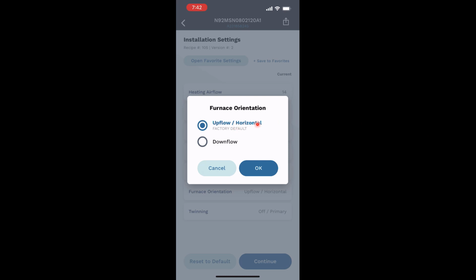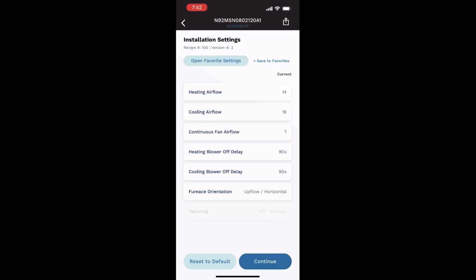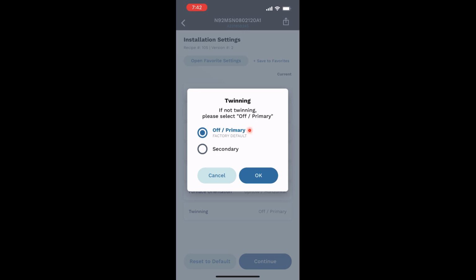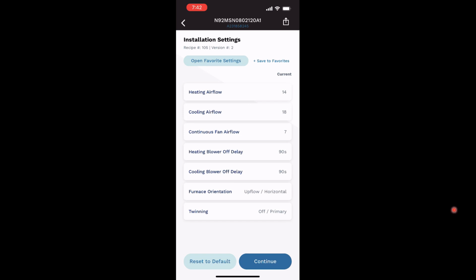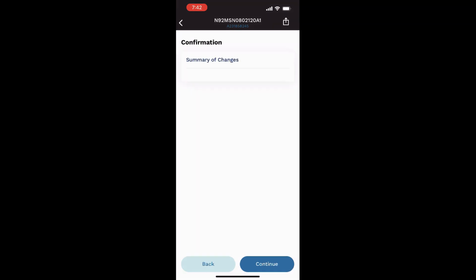And you look at, am I upflow or horizontal? Factory default is upflow horizontal, and if you're going downflow, you have to change that orientation. Then you go to the twinning, and you're either off and primary or you are secondary. Click OK, and it takes you back to this screen. And then we look at our summary of changes.